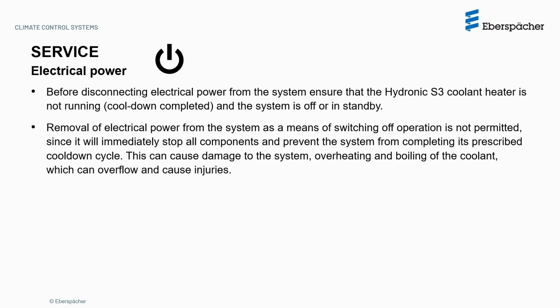The removal of electrical power from the system as a means of switching off operation is not permitted, since it will immediately stop all components and prevent the system from completing its prescribed cooldown cycle. This can cause damage to the system, overheating, and boiling of the coolant, which can overflow and cause injuries.